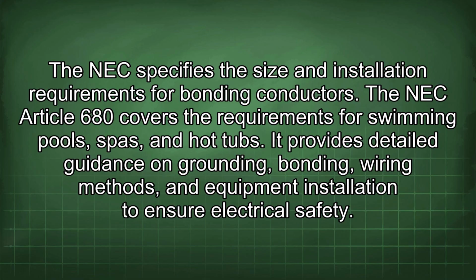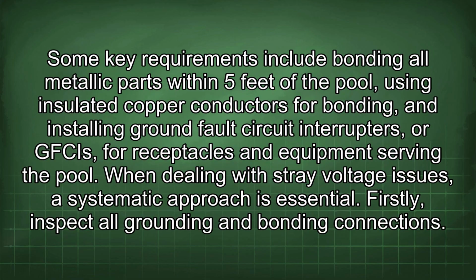The NEC Article 680 covers the requirements for swimming pools, spas, and hot tubs. It provides detailed guidance on grounding, bonding, wiring methods, and equipment installation to ensure electrical safety. Some key requirements include bonding all metallic parts within 5 feet of the pool, using insulated copper conductors for bonding, and installing ground fault circuit interrupters, or GFCIs, for receptacles and equipment serving the pool. When dealing with stray voltage issues, a systematic approach is essential.